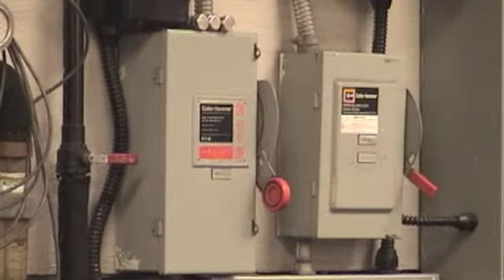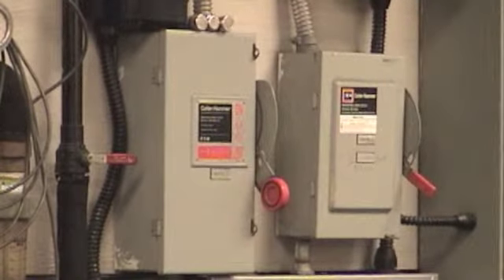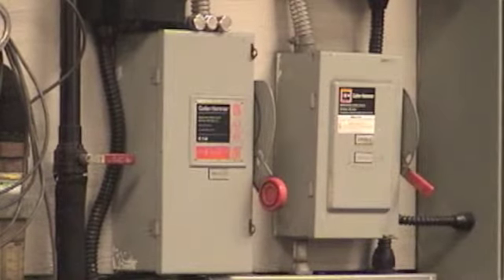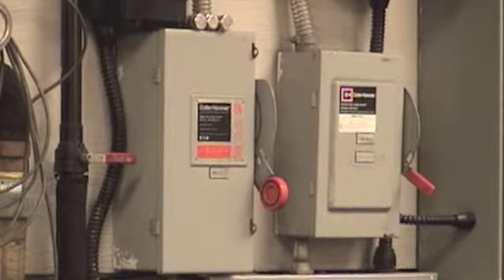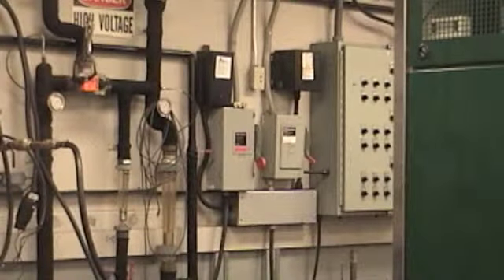Another important thing to keep in mind is the location of the electrical shutoff. You want to make sure that it's relatively close to the chiller so that you can make sure the unit is completely locked out if you have to work on any of the electrical components.